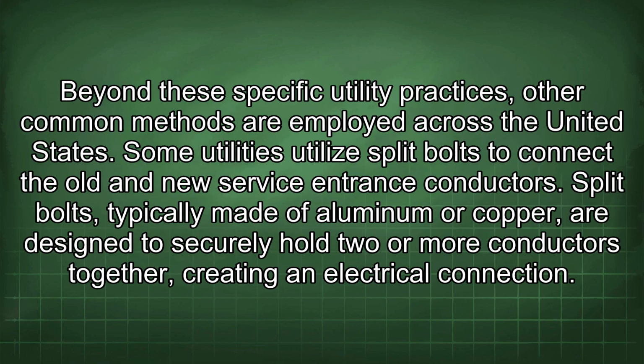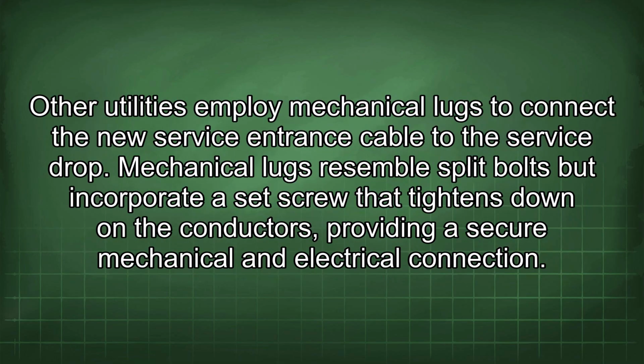Beyond these specific utility practices, other common methods are employed across the United States. Some utilities utilize split bolts to connect the old and new service entrance conductors. Split bolts, typically made of aluminum or copper, are designed to securely hold two or more conductors together, creating an electrical connection. Other utilities employ mechanical lugs to connect the new service entrance cable to the service drop. Mechanical lugs resemble split bolts but incorporate a set screw that tightens down on the conductors, providing a secure mechanical and electrical connection.